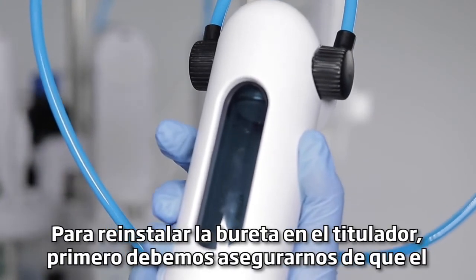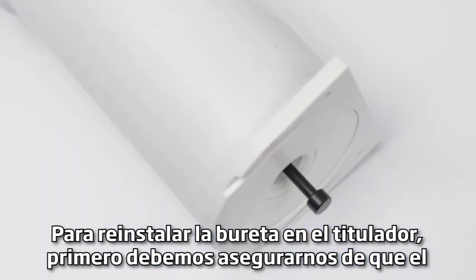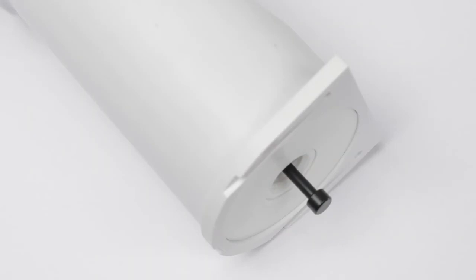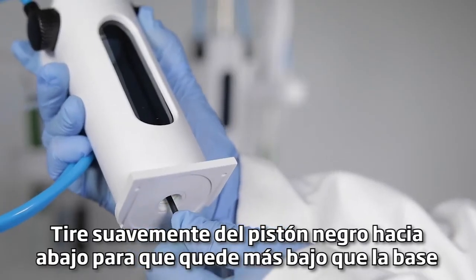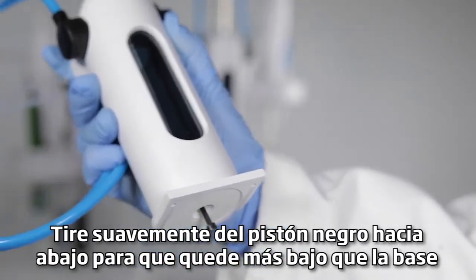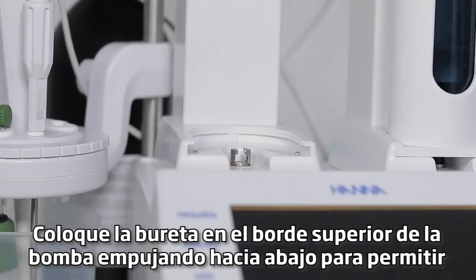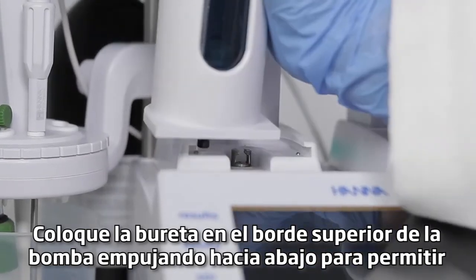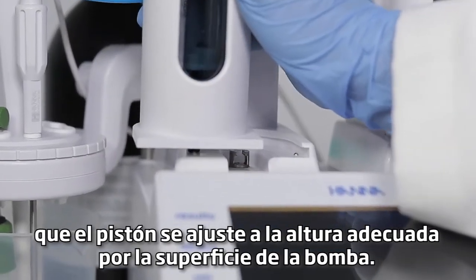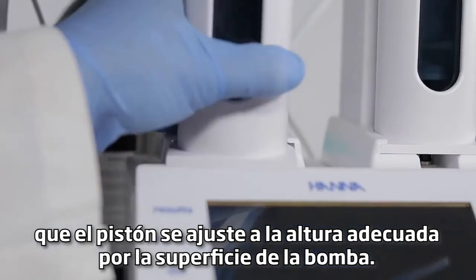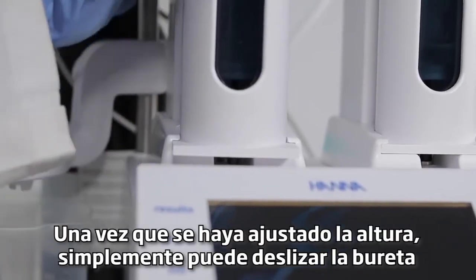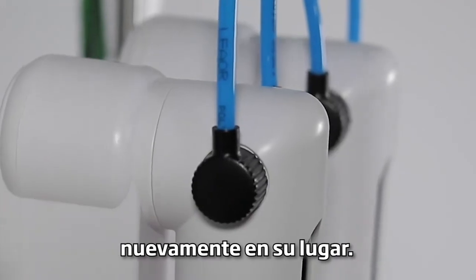To reinstall the buret on the titrator, we first have to ensure that the piston is at the correct height. Pull the black piston down gently so that it is lower than the base of the buret. Sit the buret on the upper lip of the pump, pushing down to allow the piston to adjust to the proper height by the pump surface. Once the height has been adjusted, you can simply slide the buret back into place.